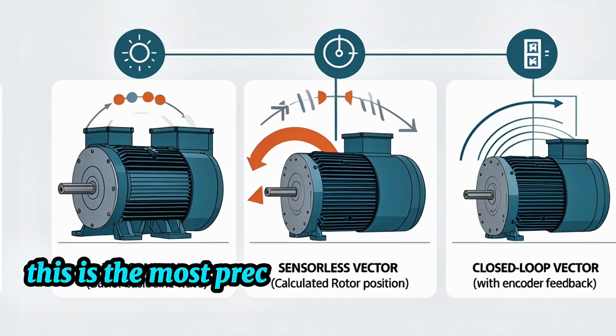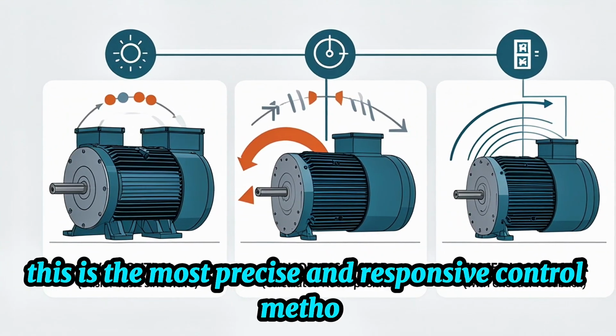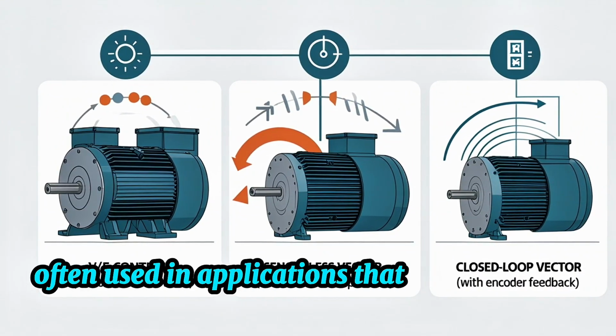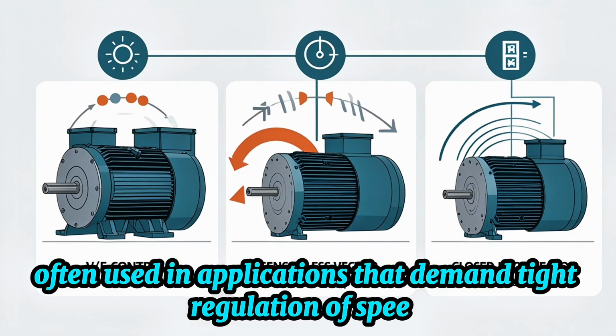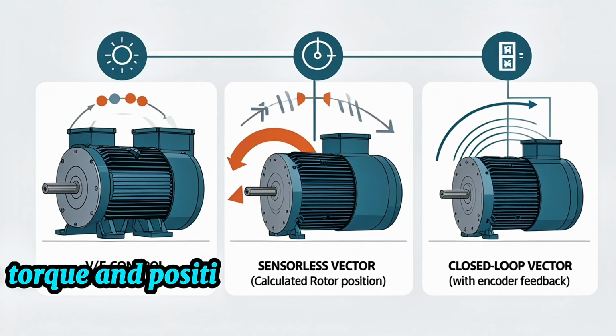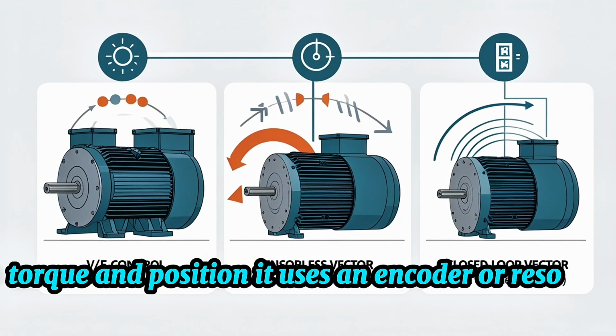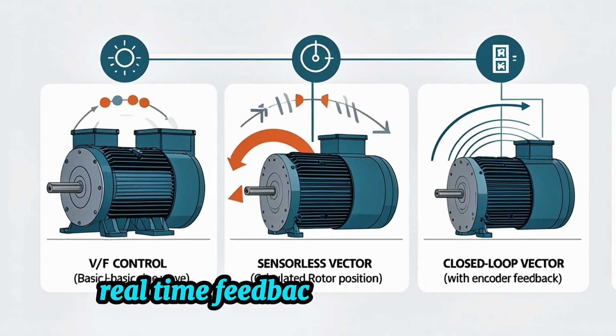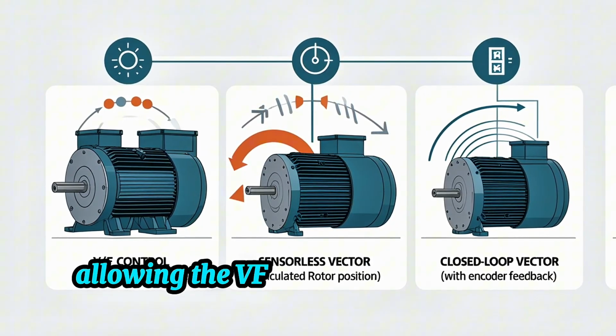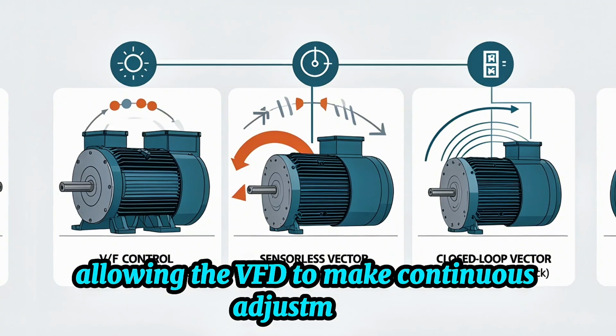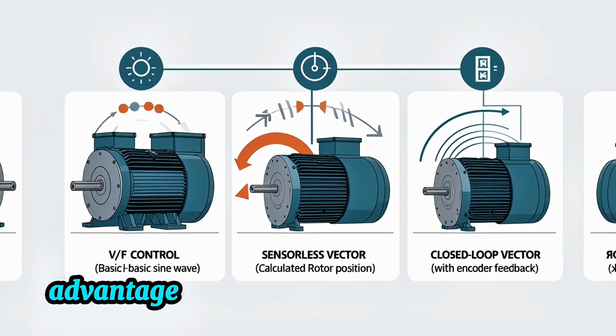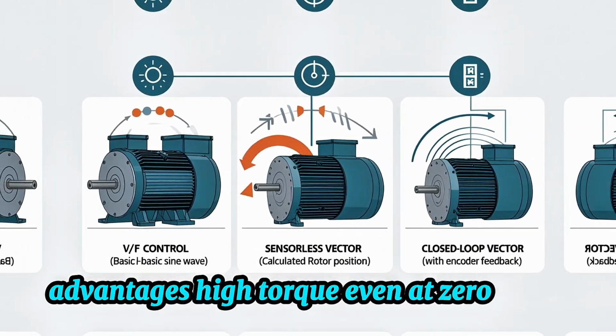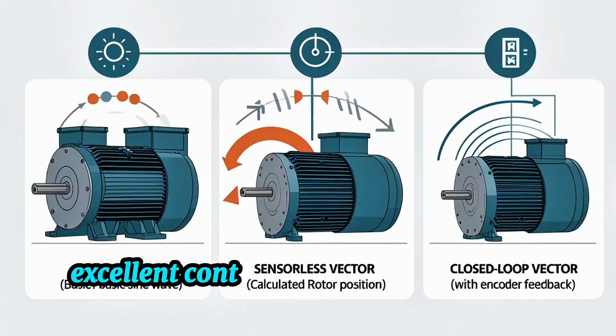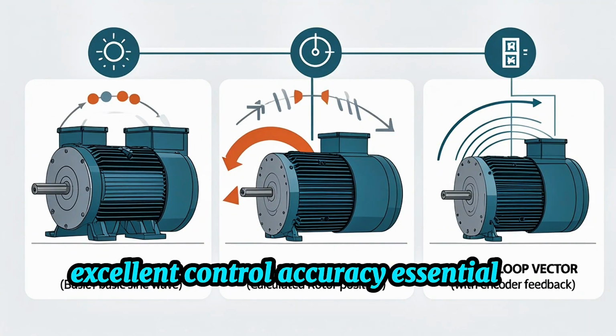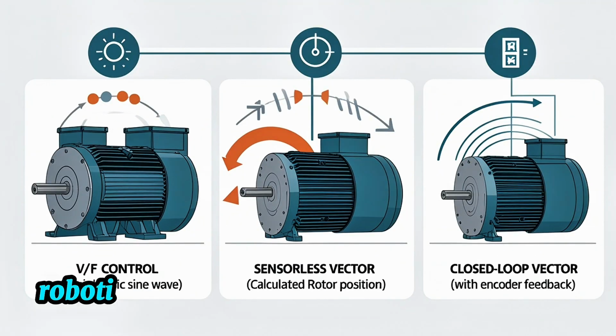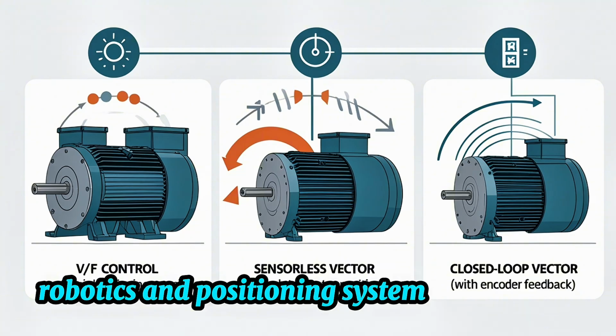This is the most precise and responsive control method, often used in applications that demand tight regulation of speed, torque, and position. It uses an encoder or resolver to provide real-time feedback from the motor, allowing the VFD to make continuous adjustments. Advantages: high torque even at zero speed. Excellent control accuracy. Essential for automation, robotics, and positioning systems.